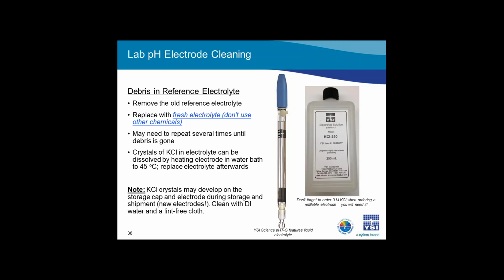If you have a refillable pH electrode and you find that the reference electrode has been contaminated, it is very necessary that you remove all of the electrolyte from the refillable sensor and replace it with fresh electrolyte. Do not try to rinse the electrolyte reservoir with anything but fresh electrolyte. You may need to repeat this step several times until all the contamination has been removed from the reservoir. If the KCl has formed crystals in the reservoir, you can dissolve them by heating the electrode in a 45-degree C water bath. Be sure to drain and replace the electrolyte after doing this.